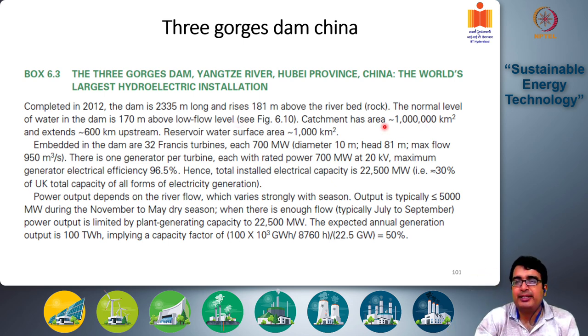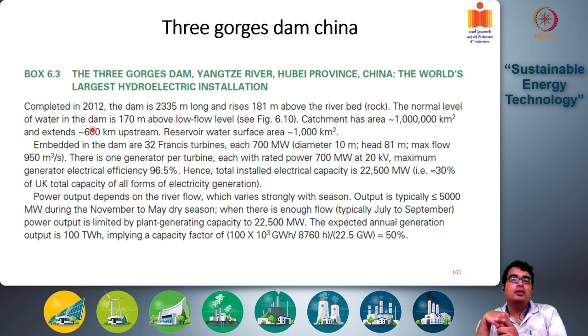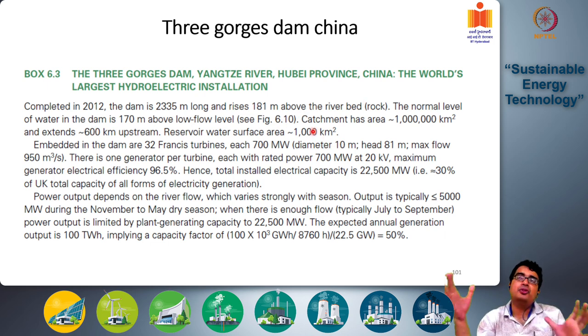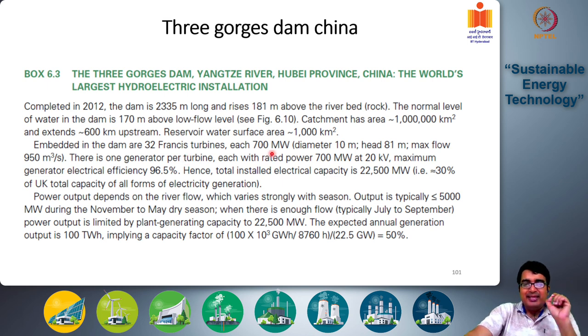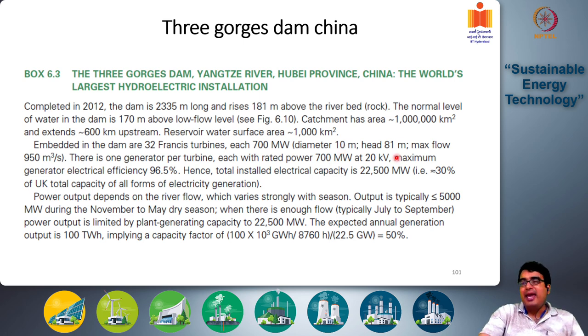The Three Gorges Dam captures water over a catchment area of more than 1 million square kilometers and extends 600 kilometers upstream. The reservoir surface area is 1,000 square kilometers. The dam houses 32 Francis turbines, each with 700 megawatt capacity. The diameter of each turbine is 10 meters, the water head under capacity conditions is approximately 81 meters, and the maximum flow rate is 950 cubic meters per second per turbine.